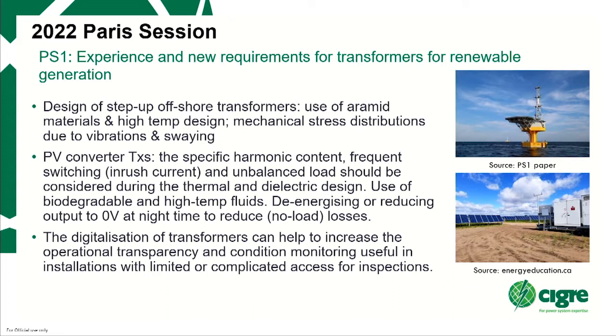This covered some of the challenges in the design of step-up transformers for use in offshore installations, including high temperature design requirements because they're installed in very small confined enclosures, and detailed design work around mechanical stress distributions due to vibrations and swaying that you get on offshore platforms that you don't see in standard onshore installations.